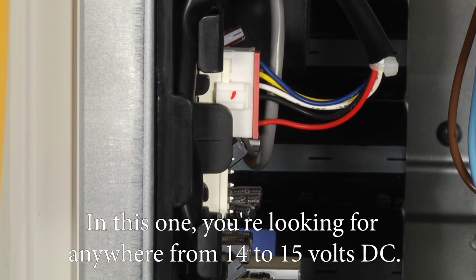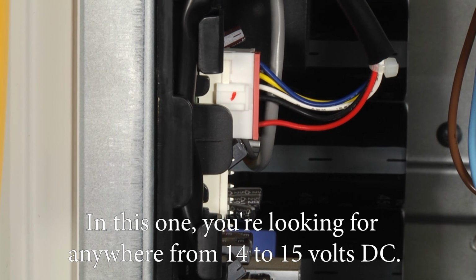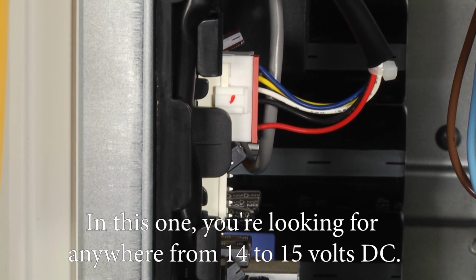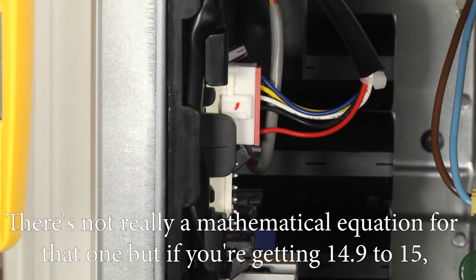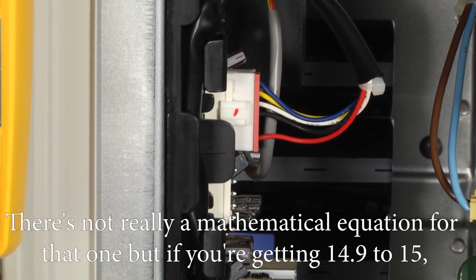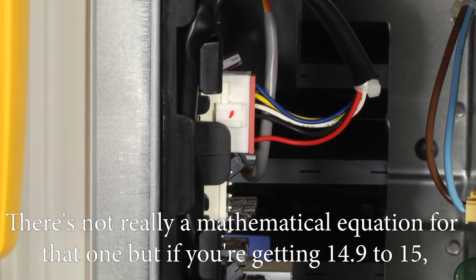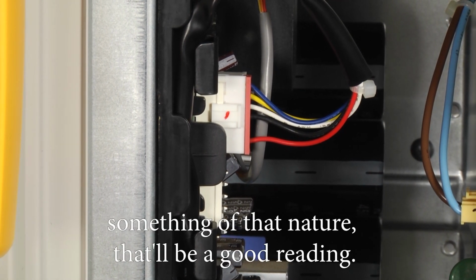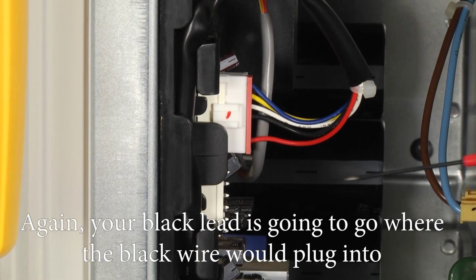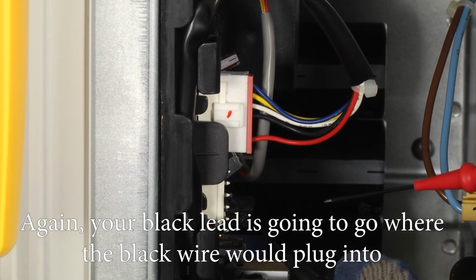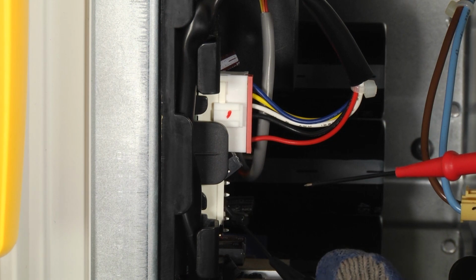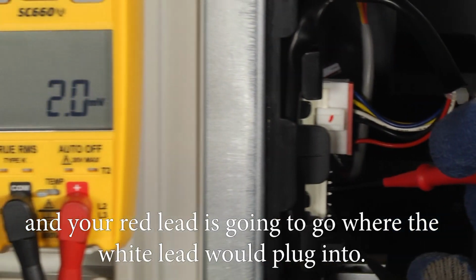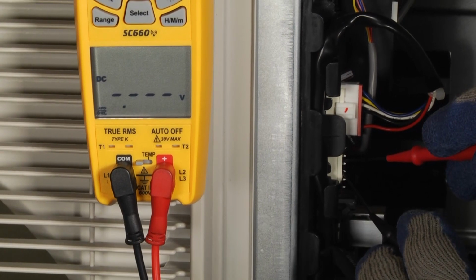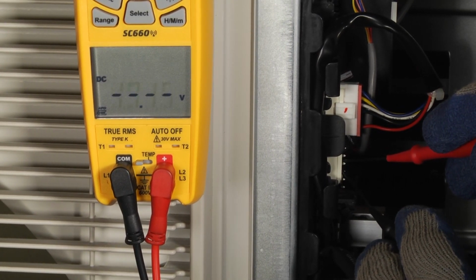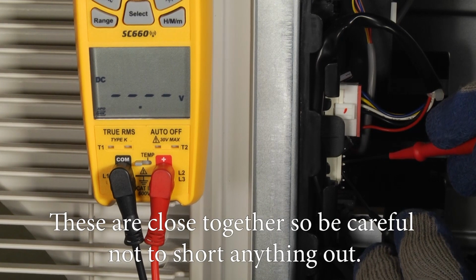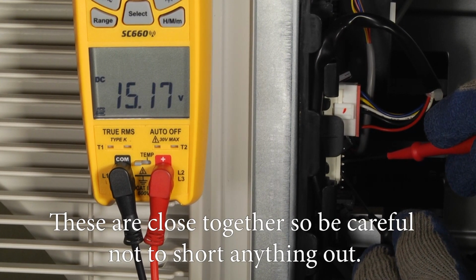And in this one, you're looking for anywhere from 14 to 15 volts DC. There's not really a mathematical equation for that one, but if you're getting 14.9 to 15, somewhere in that nature, that'll be a good reading. So again, your black lead is going to go where the black wire would plug into, and your red lead is going to go where the white wire would plug into. Get it on there. Again, these are close together, so be careful not to short anything out.